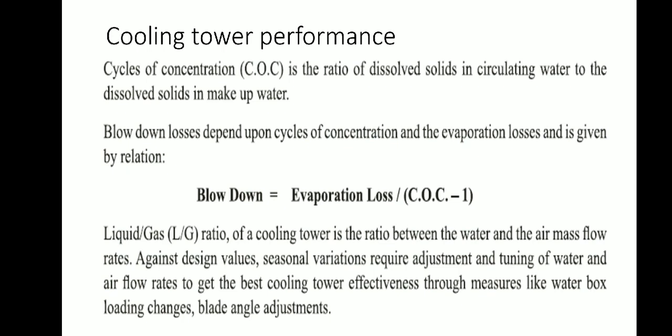Already all of you know what blow down is. Blow down is the removal of dissolved particles from the water. Then the blow down is equal to evaporation loss divided by COC minus 1, because evaporation loss is the cause for addition of makeup water. In makeup water there are some dissolved materials, therefore the cycle of concentration. Then the particles must be removed through blow down operation. Therefore the blow down loss is evaporation loss divided by COC minus 1.